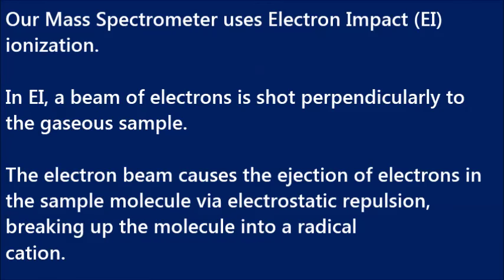Our mass spec is EI positive ionization, so it's electron impact ionization. The way electron impact works is that a beam of highly energized electrons are emitted from a filament, and the electron's path is perpendicular to the path of the gaseous molecules. As electrons move closer to the molecules, the molecular electrons are ejected from the electron cloud due to electrostatic repulsion.